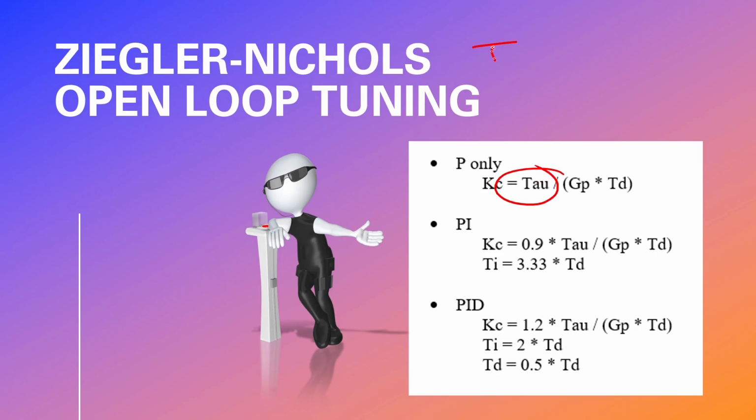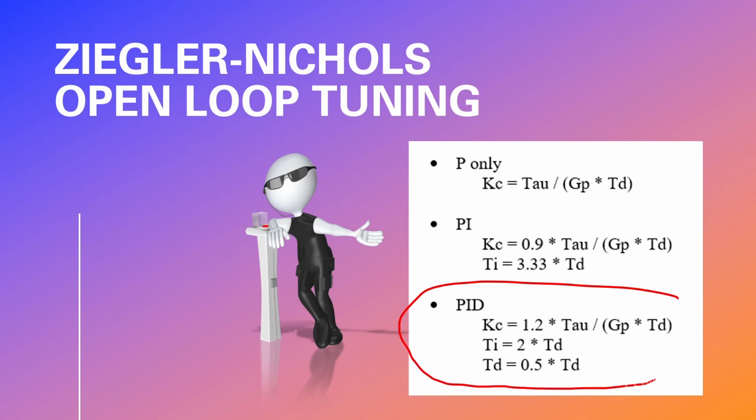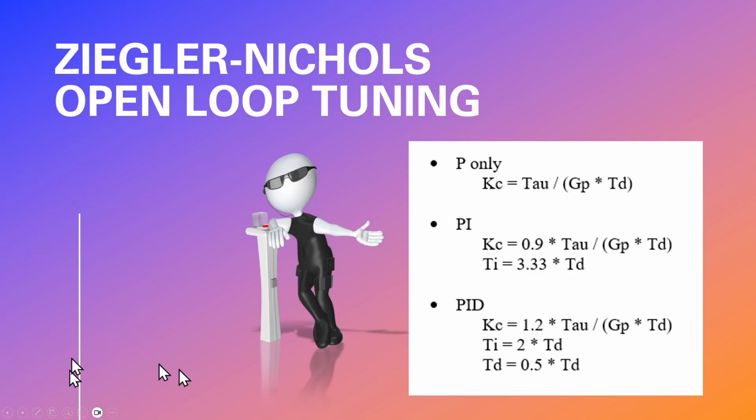Now, easy enough, just remember that tau is going to be the time constant, the time taken for the process variable to move to 63.2% of where it's going. For me, 63.2% is close to 66%, which is 2/3 of the way. And so that's what we're going to do. Now, we're going to use the bottom set of formulas, and again, don't work harder, work smarter. Put it inside a spreadsheet and it will do all of the calculations for you.